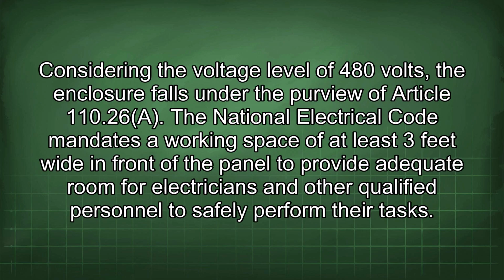Considering the voltage level of 480 volts, the enclosure falls under the purview of Article 110.26a. The National Electrical Code mandates a working space of at least 3 feet wide in front of the panel to provide adequate room for electricians and other qualified personnel to safely perform their tasks.